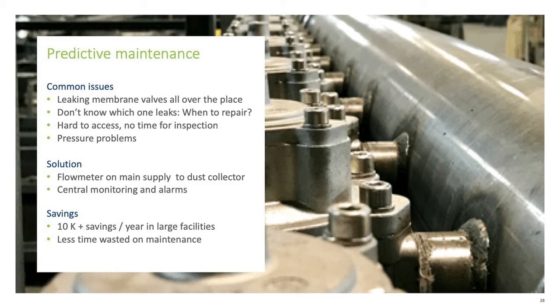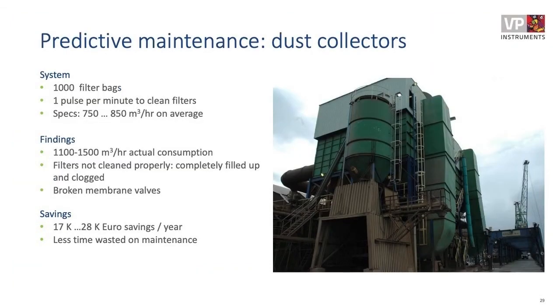So we had a case a couple of years ago in a steel plant, which I will show you. Here you see these dust collector towers. In this case, they had about 1,000 of these bag filters, which were cleaned out with 1 pulse per minute. By design, it was specified that there should be an air consumption between 750 and 850 cubic meters an hour on average. So they installed a flow meter for a temporary audit, and they found that the air consumption was much higher than specified. It was almost twice in some cases.